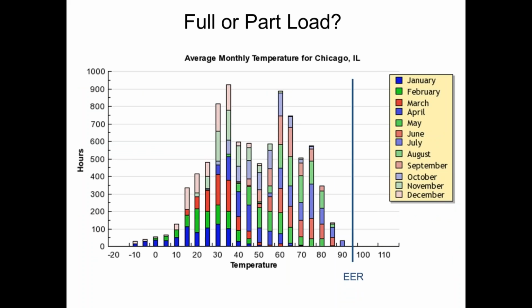If we look at those outdoor temperatures a little differently, instead of looking at the most extreme design temps, we look at a profile of all the outdoor temperatures and how many hours we spend at those temperatures, and this example is for Chicago, but we can do other cities as well, obviously. The EER of a packaged rooftop unit, or most mechanical equipment for that matter, energy efficiency ratio, is tested at 95 degrees ambient. And that tells you how efficient your unit is at that outdoor air temperature, right? But you can see in Chicago area, we don't hit 95 degrees at all on an average basis. Yeah, we'll have some random day every few years where it's 100 degrees, but on an average, like a rolling 30-year cycle, we have almost no run hours above 91, 92 degrees. So a 95-degree test point is not super interesting to us, or most of the country for that matter.